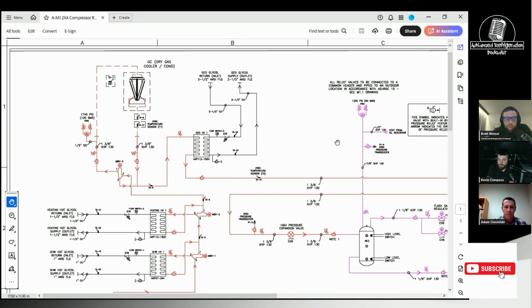Okay. So then that available liquid is used by the circuits, and any flash gas is just handled by flash gas bypass. Gotcha. And because you're condensing it, you're getting a little bit of cooler liquid coming out of that return. So you're not adding that much load to the flash tank, correct? No, there are times when you can add a little bit more load to it, because depending on the time of the defrost cycle, at first you're going to get a lot of liquid coming out because the coil's cold, it's going to condense very well. But once you've melted all the ice and the coil temperature starts coming up, the last few minutes of the defrost cycle before you terminate is going to be largely vapor. So that vapor dumps in the receiver, and then that turns into flash gas that the bypass has to handle.